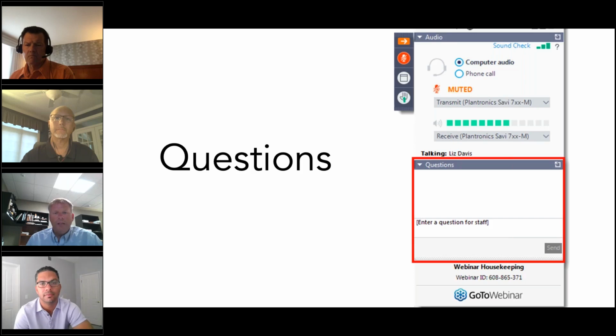That really leads back to looking at each building individually. Sometimes it's very simple changes. In our assessments, we actually put them into three groups. The first is changes the district can do immediately, like changing outside air damper settings or other easy adjustments. The second group is things that may cost something, like changing filters to a higher HEPA or higher MERV rating. The third is capital improvements, like changing air handlers or changing airflow distribution in an entire school building. So it's three different categories for looking at cost and return on investment for facilities.